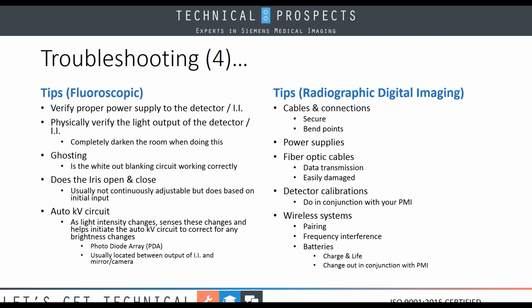A lot of systems, operators can do these detector calibrations. However, as we know, typically our operators will not do them. My suggestion to you is to do them in conjunction with your semi-annual PMs. Some of our machines today have reminders built in. A suggestion for you, if you're going to do this on a semi-annual basis, would be to set the trigger point for 7 months. This buys you a little bit of time to get your PM done and then reset the 7-month cycle again without flashing a warning that the calibration is overdue and now our operators begin panicking.